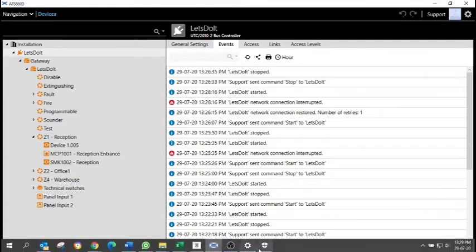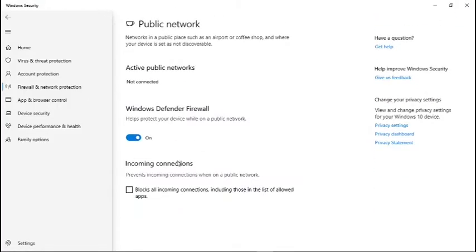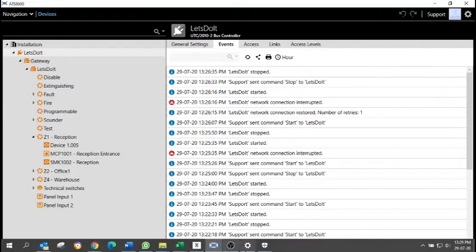What I'm showing you here is, it doesn't matter what you do at this stage, the whole ATS system is broken. What I've also found is that the fire panel still shows connected, even though nothing is happening here.